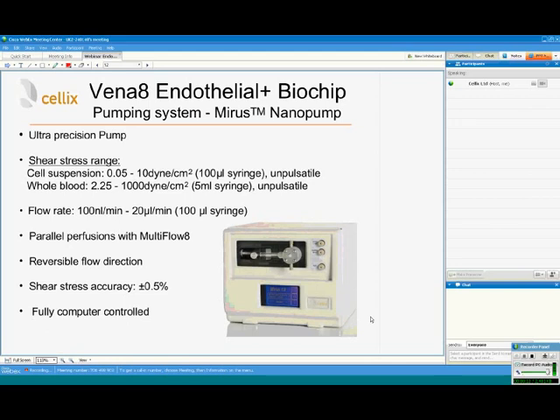To perfuse leukocytes through the Endothelial Plus biochip, we recommend using the Mirus nano-pump. It is an ultra-precision pump which allows generation of shear stress from a very low 0.05 dynes per square centimeter up to 1000 dynes per square centimeter. It precisely controls the flow and allows up to eight parallel perfusions using the MultiFlow8. The shear stress is extremely accurate and the pump is fully computer-controlled, running via VenaFlux FSI software. The pump is provided with an eight-way cable connector.